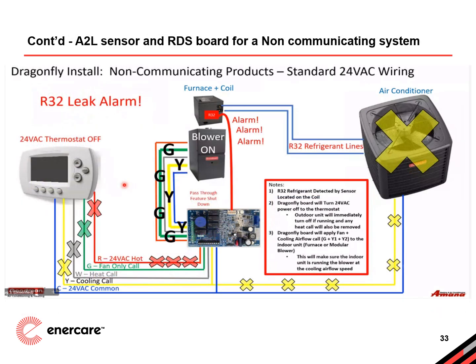So let's walk through how this RDS system steps in when an A2L refrigerant leak occurs. First, the sensor keeps an eye out for refrigerant leaks all the time. If it detects R32 refrigerant, it immediately sends a signal to the RDS control board. Once the board receives that signal, it springs into action and shuts down the 24 volts power going to the thermostat. What does this do? It completely shuts off the outdoor unit and stops any ongoing heating or cooling operation, kind of like pulling the plug for safety.